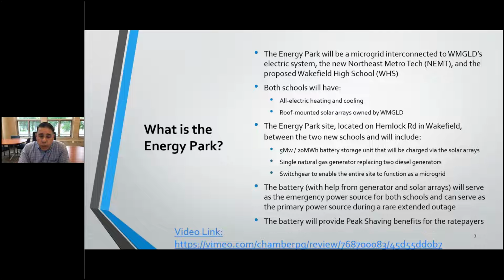They would both most likely be diesel operated. So what we did is we decided that the best way to handle this would be to site a battery in between the two schools that could serve the emergency load of both. And instead of putting a generator at both schools, we're putting a transformer that's fed directly off that battery.